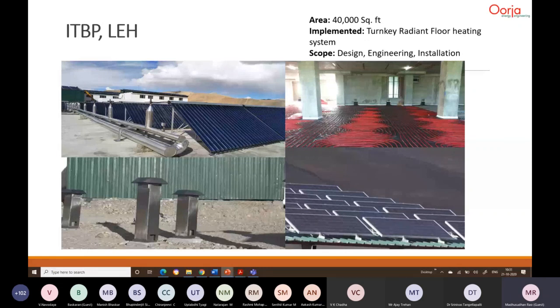This was the first such building where solar thermal heat production happens during the day, whereas the heat requirement is at night. We have a very large 35 kiloliter tank below the bunker in the basement, which stores all the hot water at 70 degrees. At night, that hot water is circulated through pipes embedded in the floor.